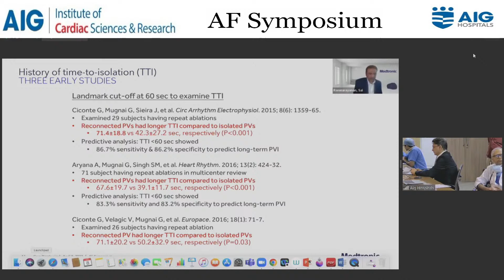And finally, Aryana and co-workers did a cryo dosing study. This is the study that we more often than not use in most laboratories across the US. So their strategy was they looked at 3 different routes. If they had a time to isolation of less than or equal to 60 seconds, then they did the time to isolation plus 2 minutes and a single freeze strategy. And if their time to isolation was greater than 60 seconds but less than 90 seconds, they would do time to isolation plus 2 minutes and an additional 2-minute freeze.